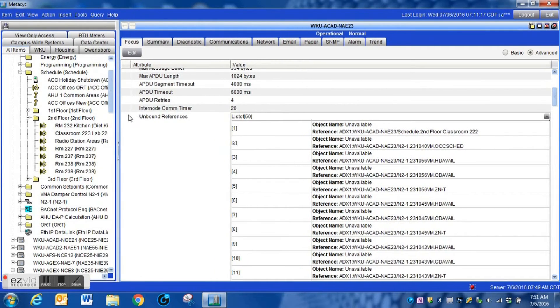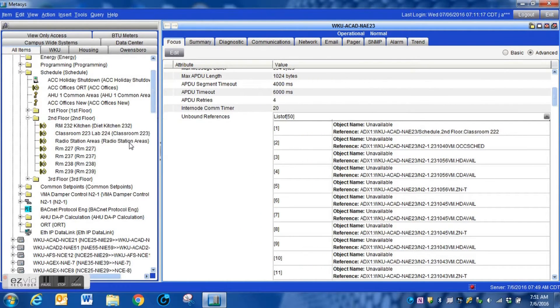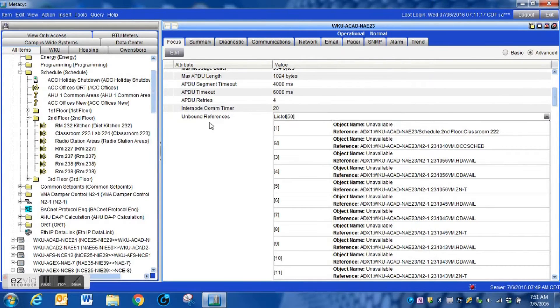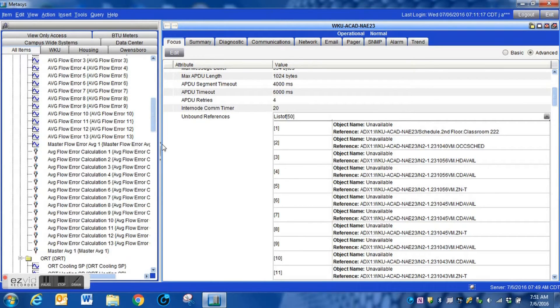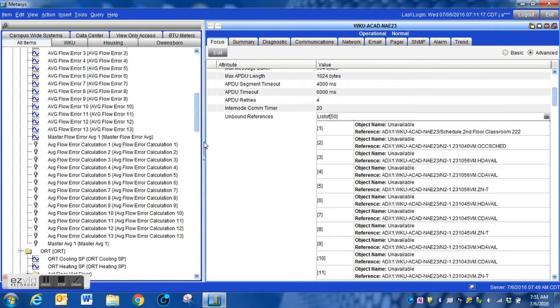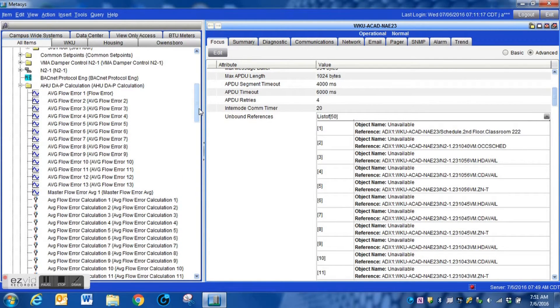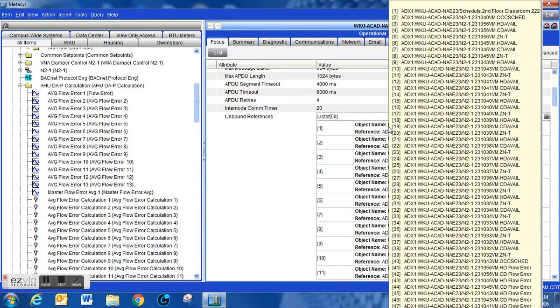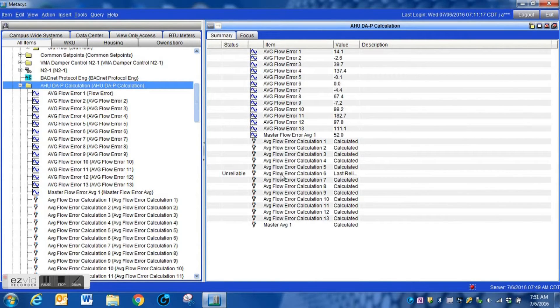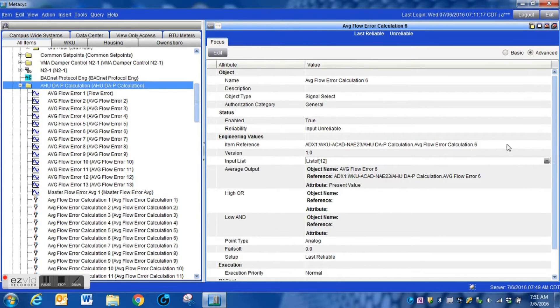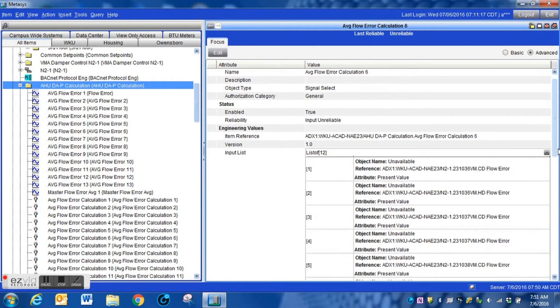The reason we have so many within this particular device is that a renovation was done in the building — several controllers were removed, office areas were added, and that sort of thing. That is a very common way for a system to generate unbound references. We're going to go through each of these items on the list, work through all of the logic, and look at schedules that may no longer be used due to those controllers being removed.